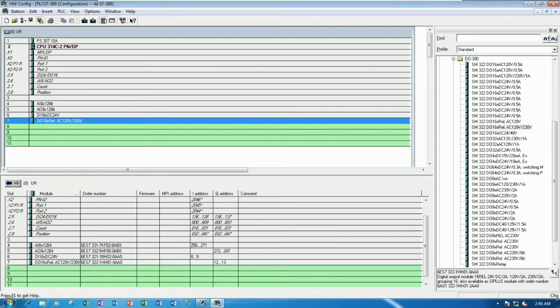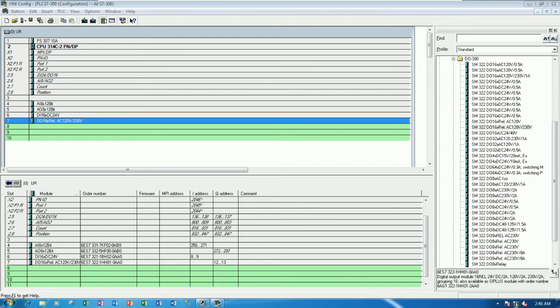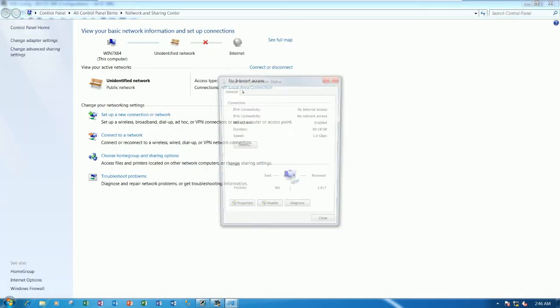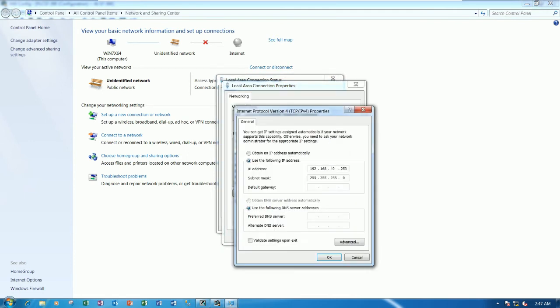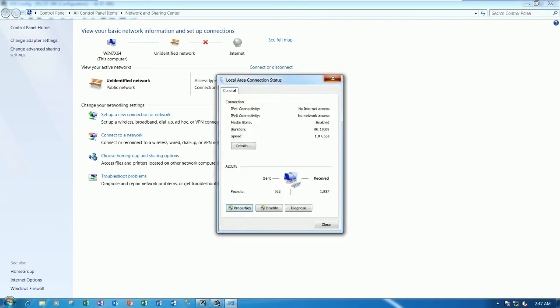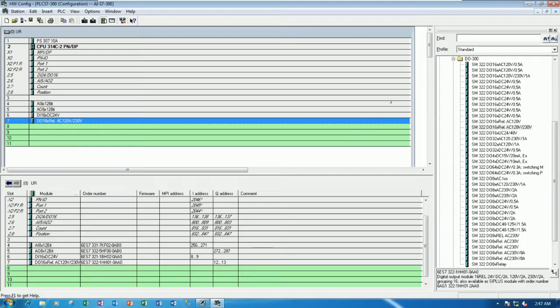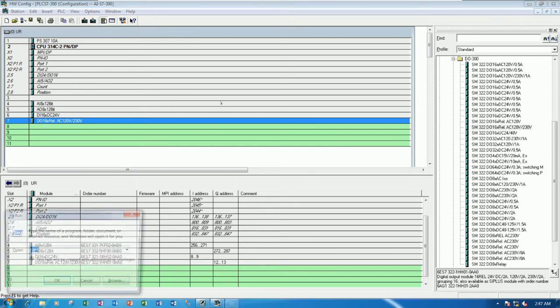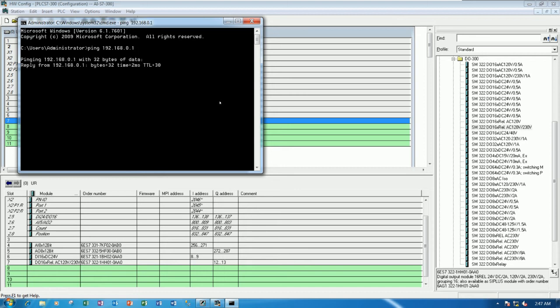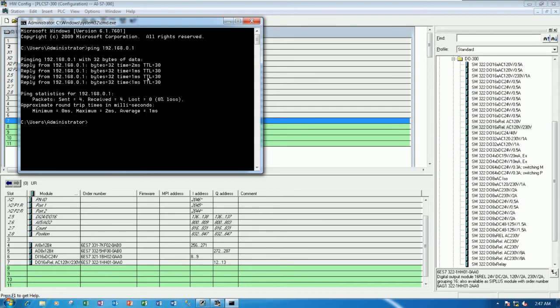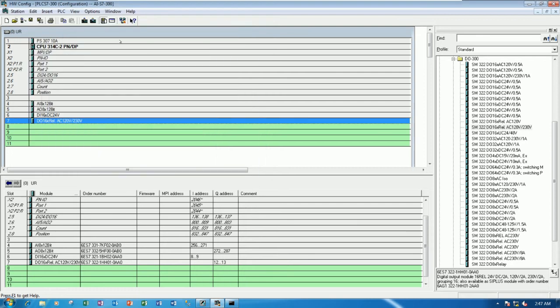So we will save the project and then we will download to the CPU. Before download, make sure we check our computer. Make the manual mode for IP address, with 192.168.0.something but not 1. Because the .1 is the address of PLC. And we can ping after we connect the LAN cable from our computer to the port of the CPU. So we can use command ping 192.168.0.1. If it reply like this, it means that we can communicate between our PC to the PLC.